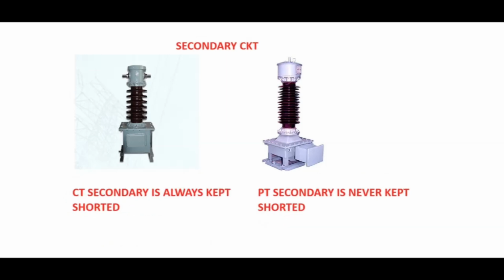Now, what is the nature of the secondary circuit? In the case of CT, the secondary circuit is always kept shorted. The CT secondary circuit is never kept open. In the case of PT, the secondary circuit is always kept open. The PT secondary circuit is never kept shorted.